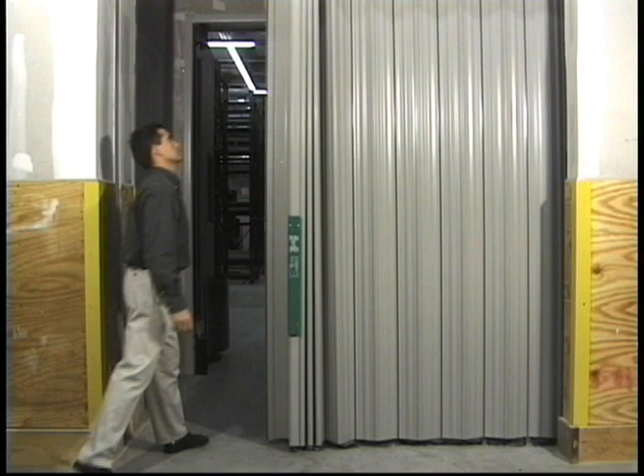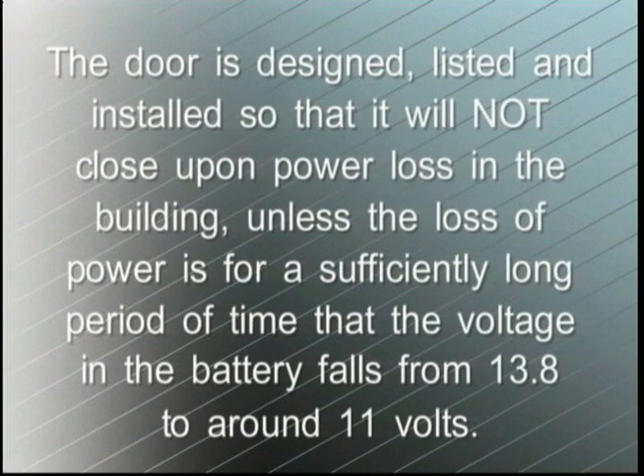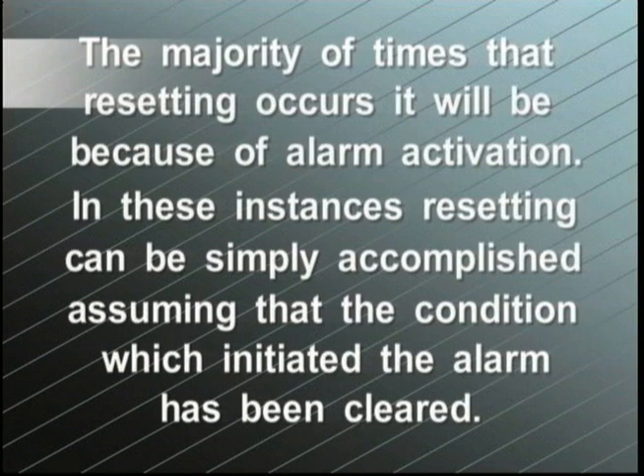The door is designed, listed, and installed so that it will not close upon power loss in the building, unless the loss of power is for a sufficiently long period of time that voltage in the battery falls from 13.8 to around 11 volts. This will substantially reduce, if not virtually eliminate, the nuisance of resetting due to power interruption. Consequently, the majority of times that resetting occurs it will be because of alarm activation. In these instances, resetting can be simply accomplished assuming that the condition which initiated the alarm has been cleared. Resetting the system is easily done by pushing the open close switch.